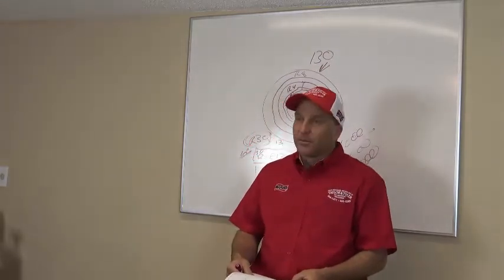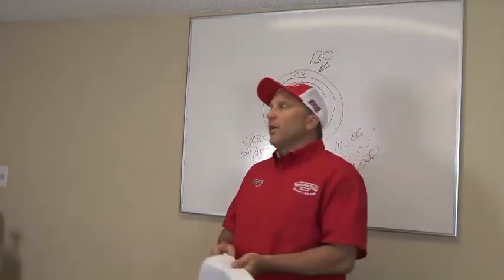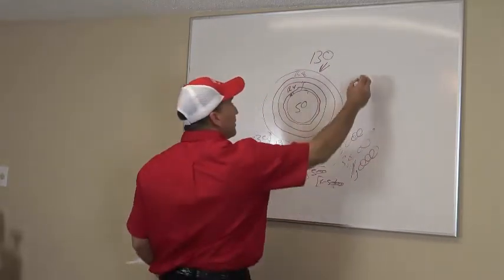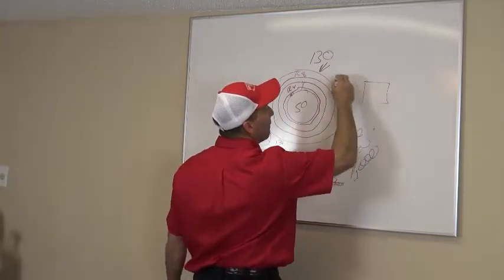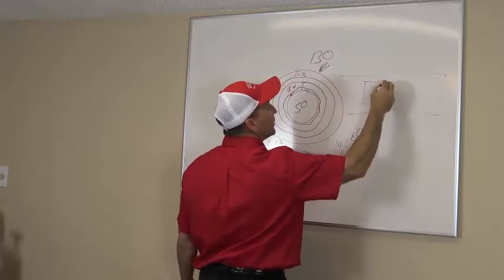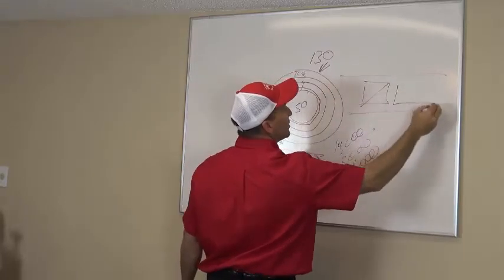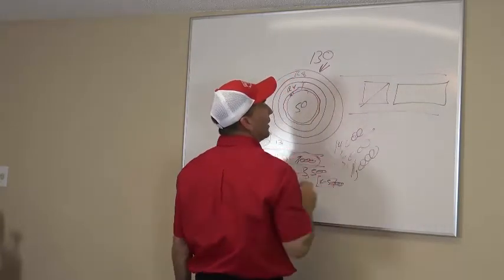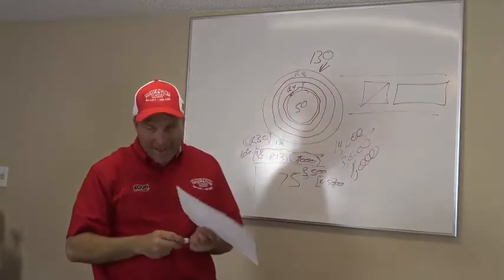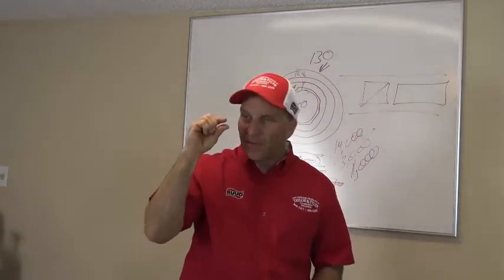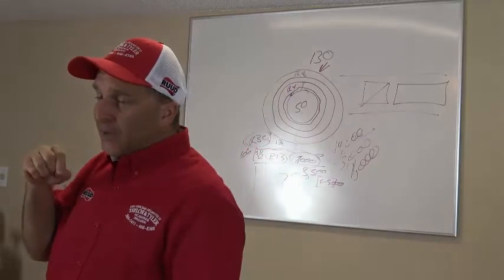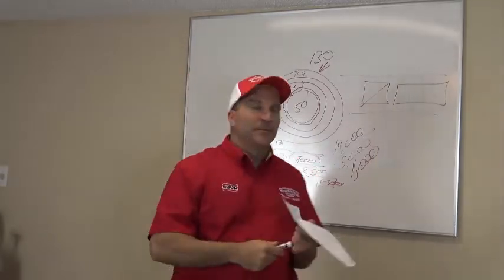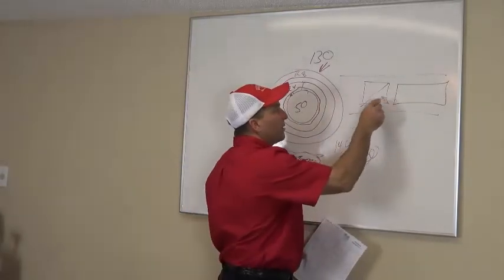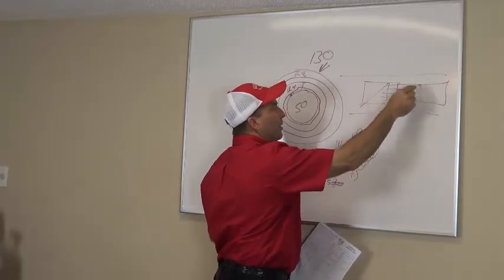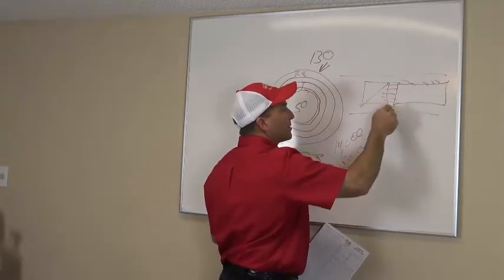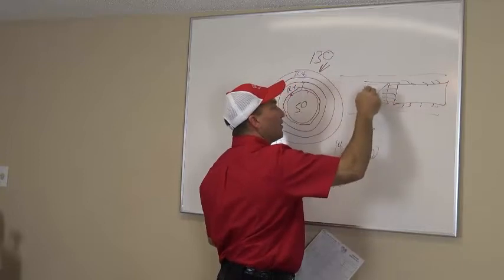Attic stairs. There's a return air grill right here, guys, in the hallway. There's your return grill. Here's your attic stairs. Right? That attic stairs hangs down a half inch. Guess what's happening in that return grill? Sucking that air. You're sucking air right into that return grill, all the way around it, right? It's sucking air and it's going right into your return grill.